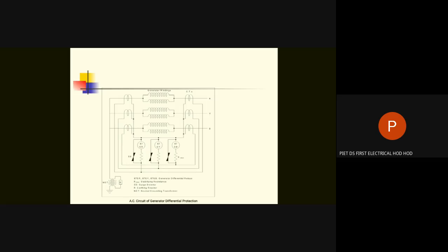Six CTs are required, as you are seeing, and the relays 87 GR, 87 GY, and 87 GB. Slowly you will have to be conversant with these numbers. These numbers are ANSI numbers, American National Standards Institute numbers. They are internationally known numbers. 87 is for differential relay. 87 G means generator, R, Y, B phases. The stabilizing resistances are also shown.